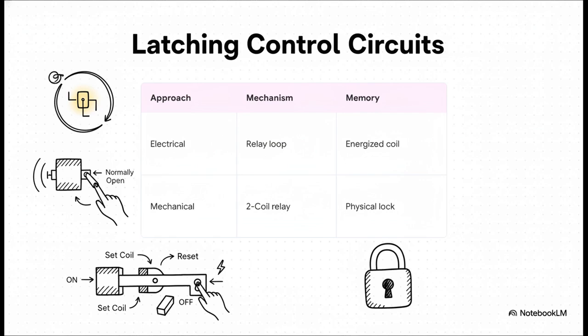It's a two-coil system. When a brief pulse of electricity hits the first coil, the set coil, an internal physical mechanism, or sometimes even a permanent magnet, physically flips a switch arm to the on position and physically locks it there. And this brilliantly highlights a huge difference. Once it's mechanically locked, you can completely cut all the power to the panel, and that switch stays locked on forever. It requires literally zero electricity to maintain its memory. It's only going to flip back off when you send a brand new electrical pulse to the second coil, the reset coil.